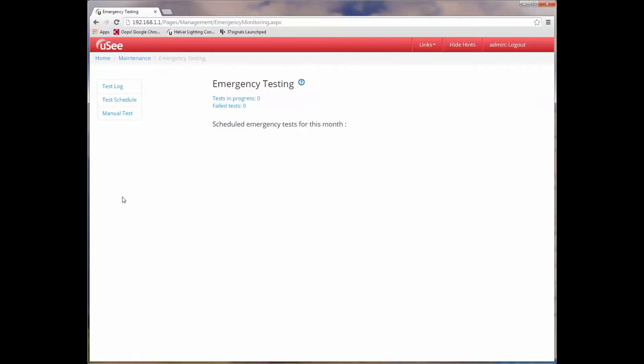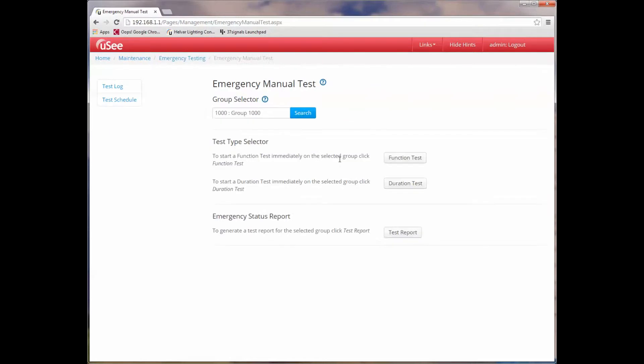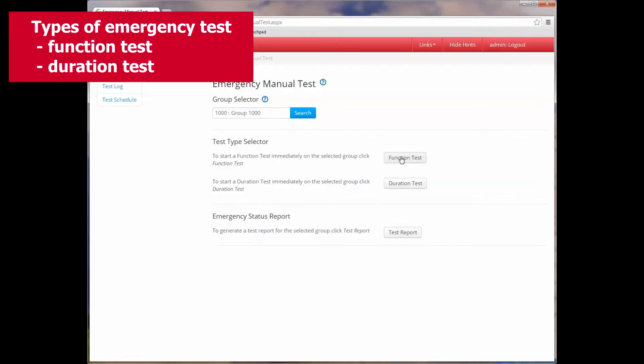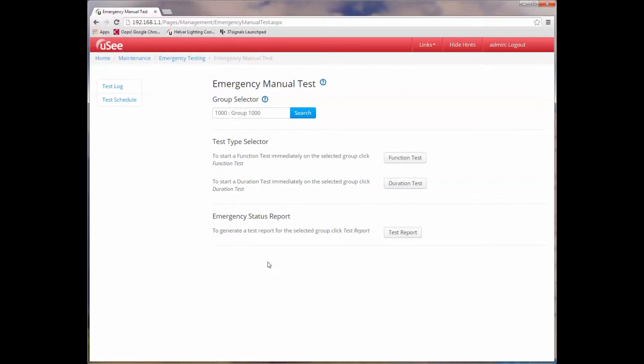This brings up some further choices: test log, test schedule, and manual test. Let's start by looking at manual tests. Having selected the manual test page, you'll notice you have the opportunity to either perform a function test, a duration test, or actually to generate a test report. The function test checks the operational status of all emergency devices in a targeted group. The duration test checks that the battery associated with each device within the emergency group is operating according to the manufacturer's specification.